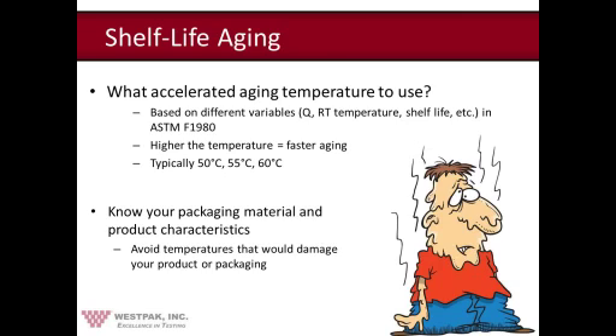Accelerated aging follows ASTM F1980. This is based on the Arrhenius equation, which shows that an increase in temperature increases molecular activity in a material, which in turn speeds up the adverse effects of aging. So the time and temperature to use is going to be based on different variables. These variables are aging shelf life, real-time temperature, aging temperature, and the Q factor, which are all defined in ASTM F1980.